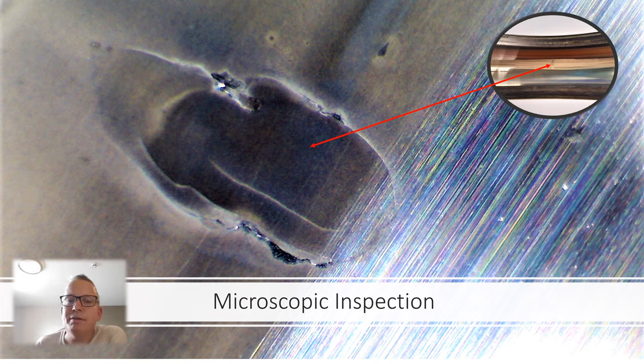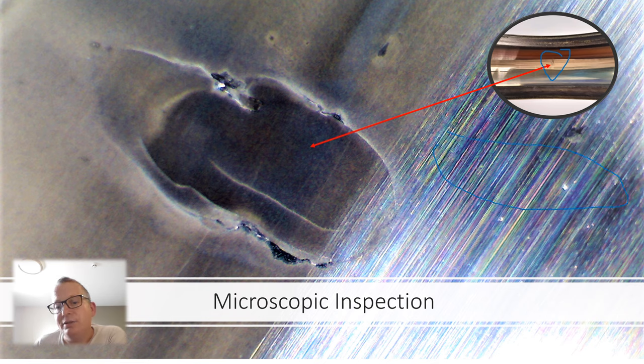And under a microscope here, and here we can see cracks, subsurface cracks starting to lift. And you can even see here, all this bit here, that's the grinding marks when they made the bearing, which is this bit here.